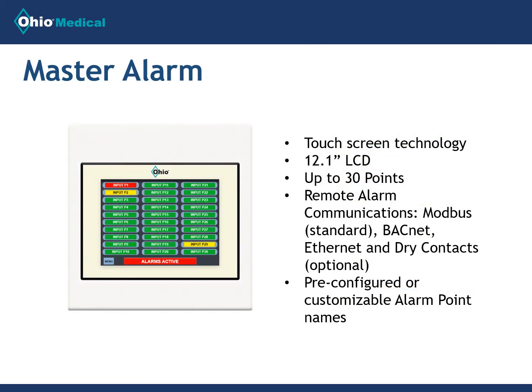Our master alarm has touchscreen technology. Its 12-inch LCD is one of the largest screens available. Fully compliant with NFPA 99 guidelines, this alarm can be programmed in either English or Spanish. It features standard Modbus remote alarm communications, or BACnet and Ethernet options. Up to 30 alarm points are available. Standard source alarm points are programmed, and custom points can be added in the field. It is assembled in the U.S. in our ISO and FDA compliant facility.